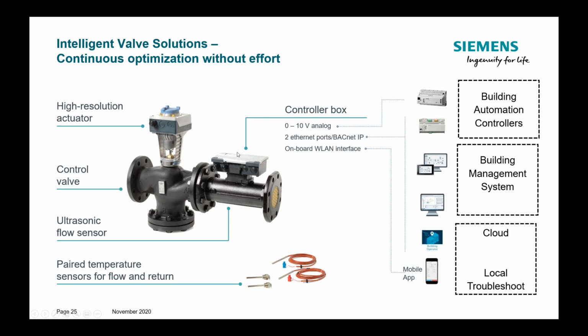This is this controller box here, which can on the one hand take care of the local optimization functions. Here we can limit the DeltaT, we can measure the power and control the power, and also limit power if needed. And this control box is also there to provide all this local information into the building automation network, to the building automation controllers. There we can deal with this information to optimize the comfort control loop, and also integrate it into the building management system. We can do the supervising, we can do trending for later optimizations. We see alarms, and we can do energy reporting.